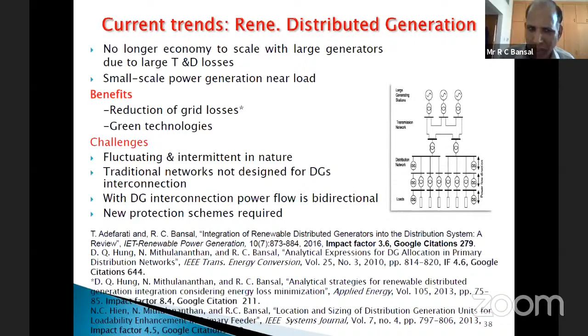Now, when we are integrating DG to the grid, there are certain grid code requirements. There is one standard, IEEE 1547, and several countries have developed their own grid codes to provide guidelines for distributed generation interconnection to the utility. IPPs will connect their DGs to the grid, but they have to follow certain requirements before connection to maintain the quality of the power supply. Some of the requirements are fault ride through capability, voltage and frequency operating limits, active power control, reactive power control, and other requirements in terms of power quality, protection, etc.